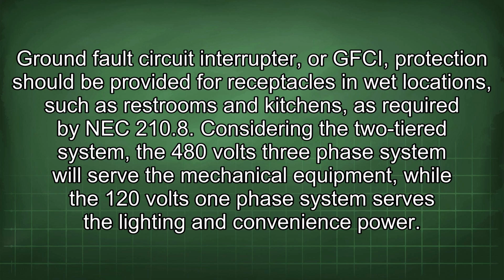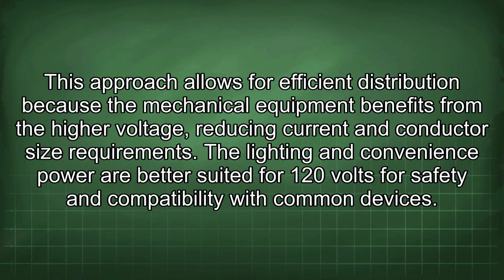Considering the two-tiered system, the 480 volts 3-phase system will serve the mechanical equipment, while the 120 volts 1-phase system serves the lighting and convenience power. This approach allows for efficient distribution because the mechanical equipment benefits from the higher voltage, reducing current and conductor size requirements. The lighting and convenience power are better suited for 120 volts for safety and compatibility with common devices.